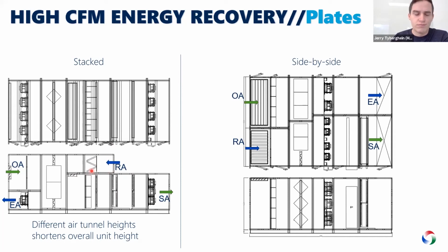A wheel, being a square, would force you to have 80 on the bottom and potentially 80 on top. So this saves about 4 feet in height. On the right, the side-by-side unit, outside air comes in here, crosses over, and supplies out. Return air comes in here, crosses over, and exhausts out here. So just another example showing how we can vary the aspect ratios as we go. You have more width over here, less width over here because you don't really have any high CFM or high face velocity components. So side-by-side and stacked arrangements, indoor and outdoor.